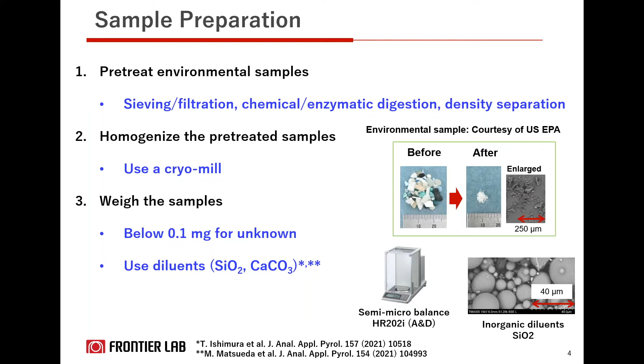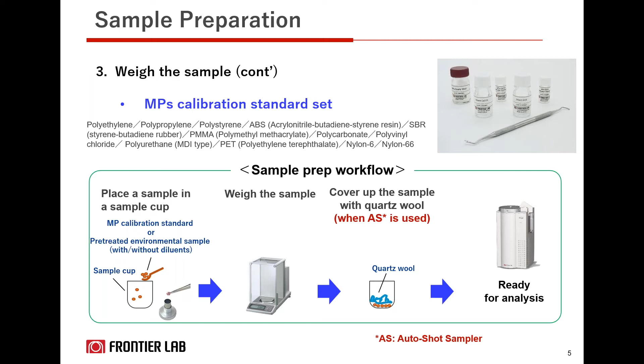So here is the overall sample preparation flow. You place your environmental sample or the microplastic calibration standard into your sampling cup. You weigh your sample, and then if you're using the auto-shot sampler, we suggest that you cover the sample with quartz wool to protect your sample, and then start your analysis using the microfurnace.